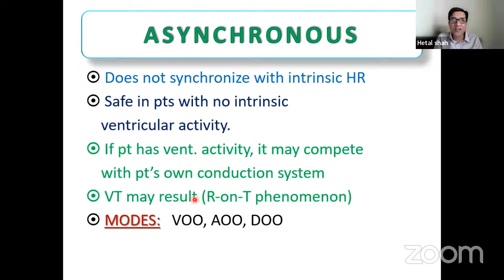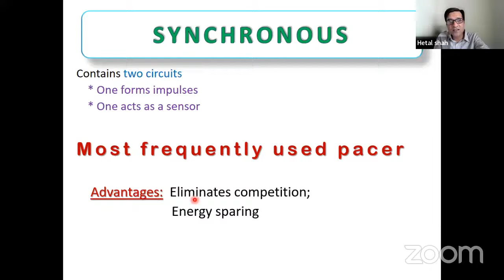So how do you know that this patient is on an asynchronous pacemaker? You see the mode of the pacemaker. If it is VOO, AOO, or DOO, that means this patient has an asynchronous mode of pacing, right? The other is the synchronous pacemaker. This is the most frequently used pacemaker, and the advantage is that it eliminates the competition. Whenever the patient's intrinsic activity comes, it doesn't pace, right? And that's why it is more energy sparing, because it uses less battery, so battery replacement becomes very late. These are the most frequently used pacemakers, and they are very useful to the patient also.